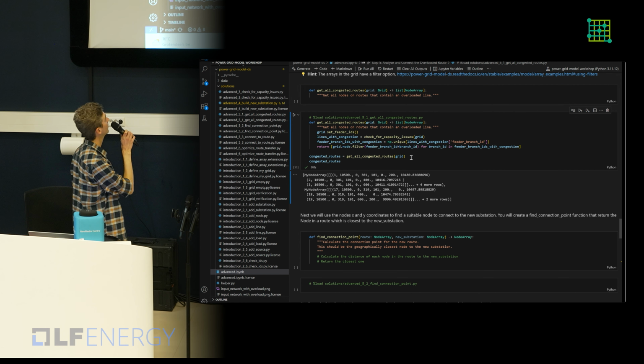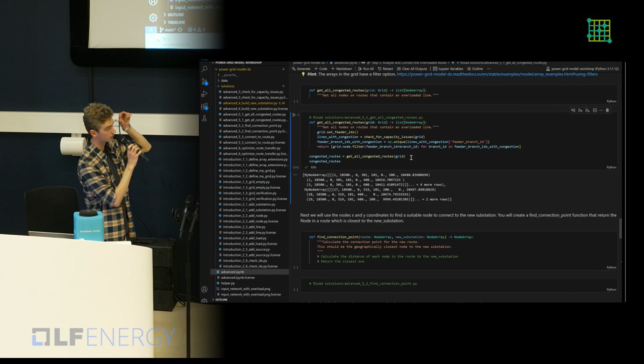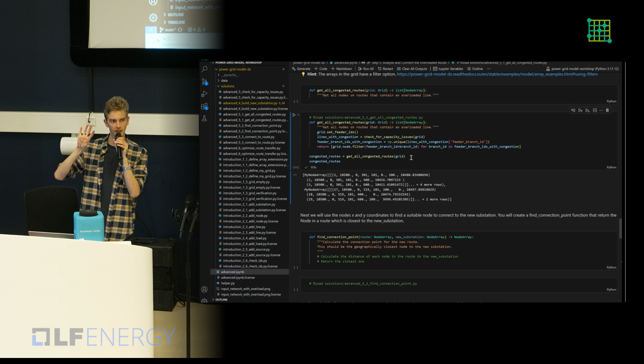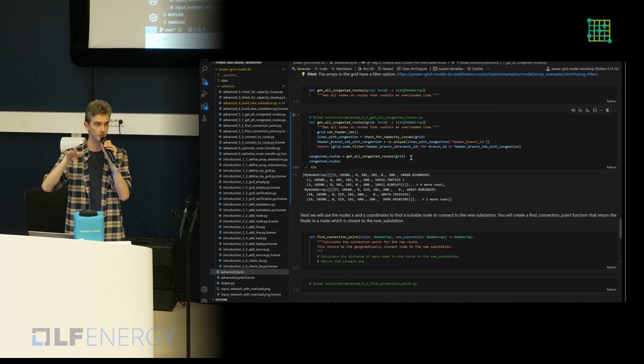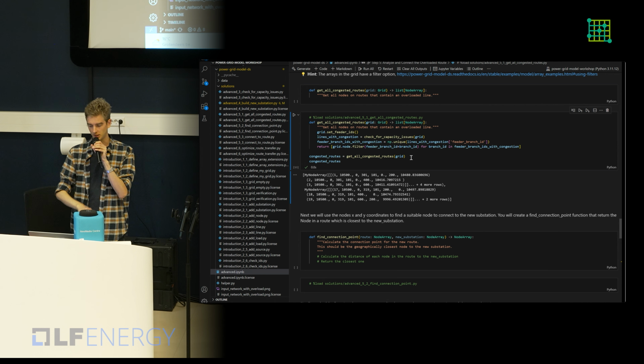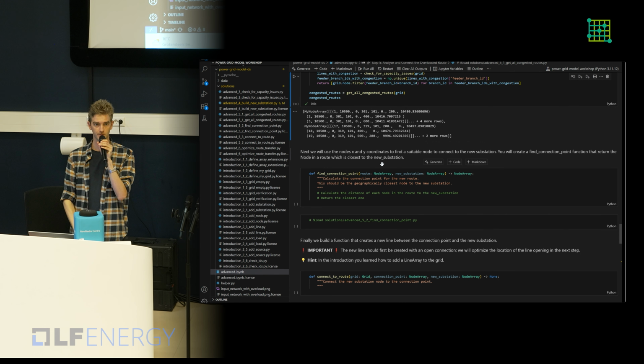Look, now we have some data. So we can see that there's 2 routes that currently have congestions on them. This also matches our image, right? We had 4 lines that were overloaded, but these 4 lines were part of 2 routes. The other 2 routes starting from the substation had no congestions. Okay, questions about this?